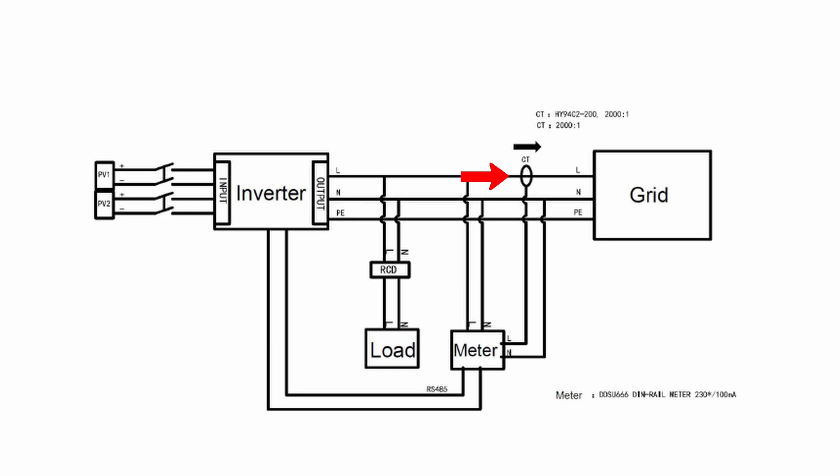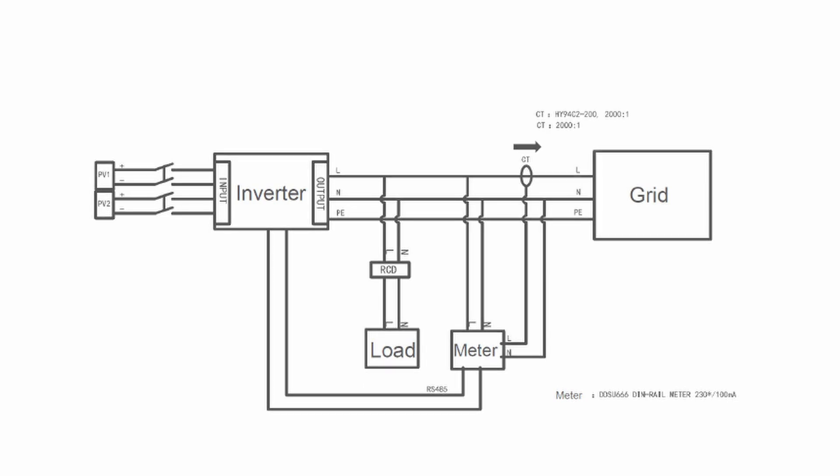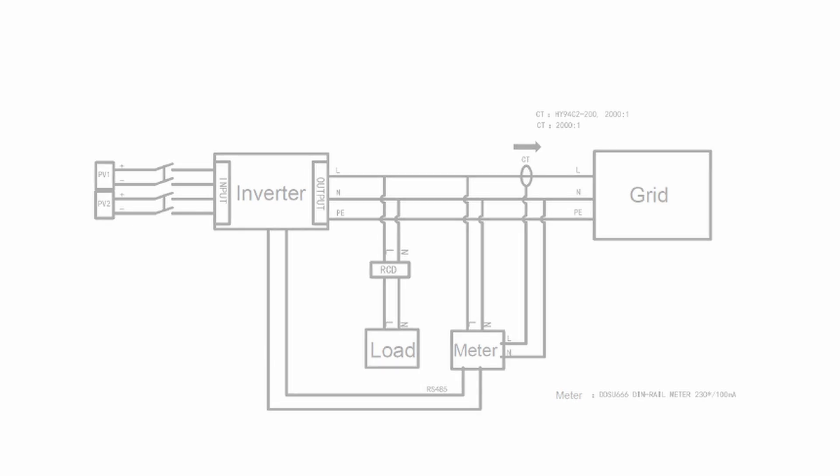Then you have your CT connected from the meter. Same principle as before - the arrow on the CT needs to point to the grid. Then the meter RS needs to be connected to the inverter via pins 5 and 6 for the RS485.